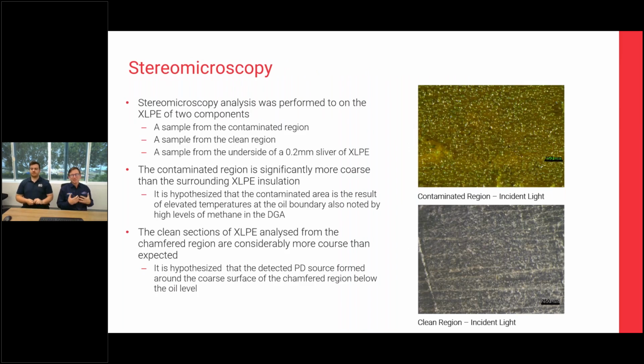This is where the analysis gets really interesting, from my point of view anyway. The stereo microscope was the last-ditch effort to try and find some forensic evidence that could lead us to a conclusive conclusion. A stereo microscope is your typical microscope, looking at the very top surface of the XLPE. Again, three of those samples were looked at: the contaminated region, the clean region, and the underside sliver. The contaminated region was far more coarse than we would have expected, and definitely far more coarse than the surrounding XLPE. So we hypothesized that the contaminated region associated with that chamfer had elevated levels of temperature, being also at the oil boundary, and the high levels of methane in the DGA indicate that.